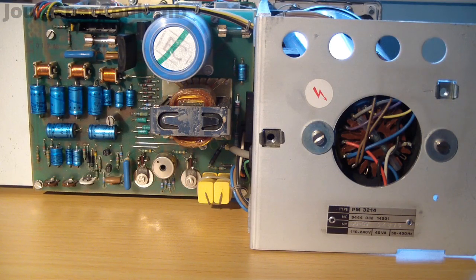Here's the rear of the instrument. There isn't a great deal to see here other than the power supply board on the left. As alluded to earlier, this takes a single AC input from the mains transformer or a DC input from an external power supply, and it generates all of the supply voltages needed. Most of these are fed to the upper PCB, which I'll show you in a moment, via these wires over here. It also generates a high voltage AC output, and that's fed to this grey cable down here.